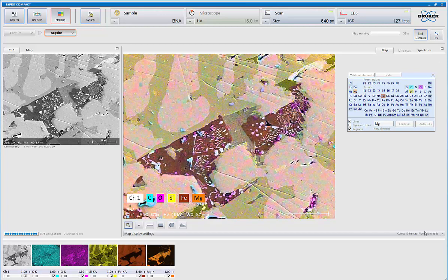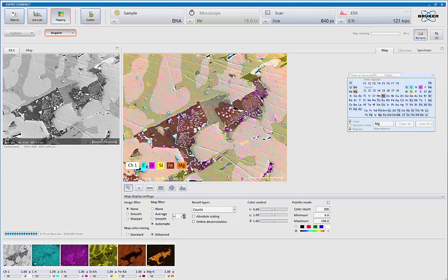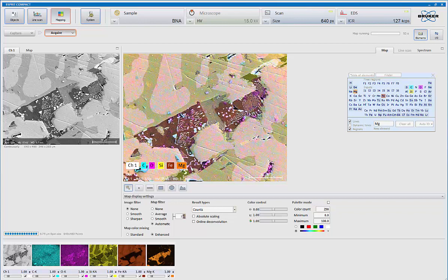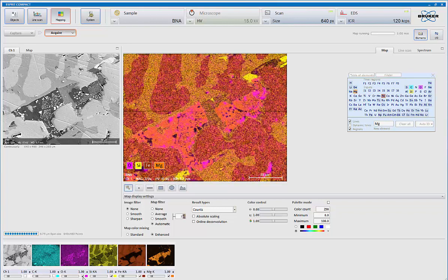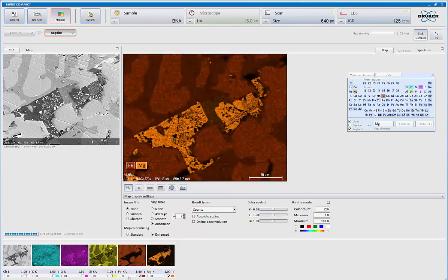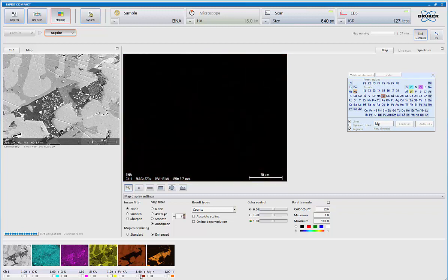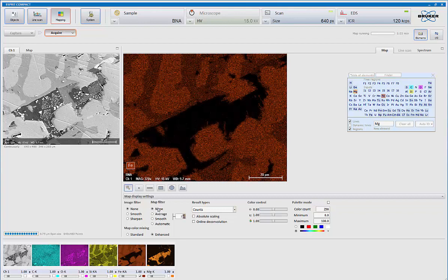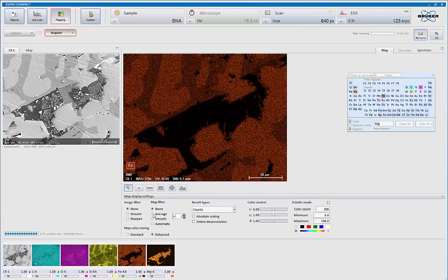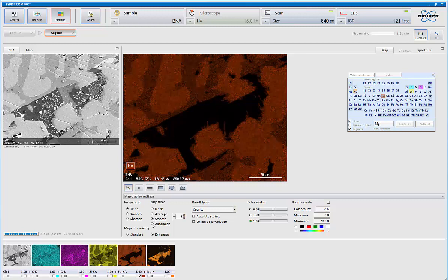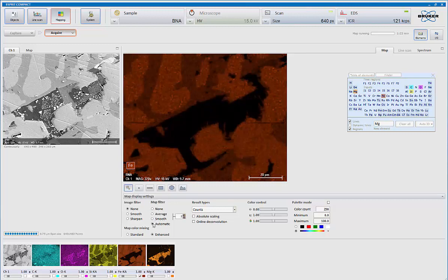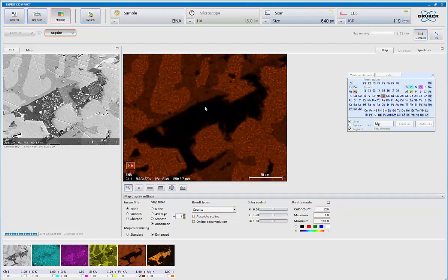At this point in time, I also have other controls located here, so I can do dynamic averaging of the maps themselves, which is a nice tool sometimes, particularly when we first start collecting, to kind of see where the major groupings of elements are. Using these check boxes, I can turn off what maps I'm viewing together, and I can then turn the averaging off at any point in time, and we can see what the functions do. That's a three-point average versus a three-point smooth versus an automatic, which is a combination of the two based on the current statistics. This is a nice tool sometimes to see groupings when the statistics are poor. Once the statistics have improved, this is a function typically we don't need to use, and we can turn that off.